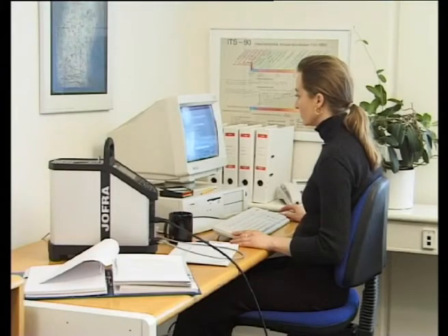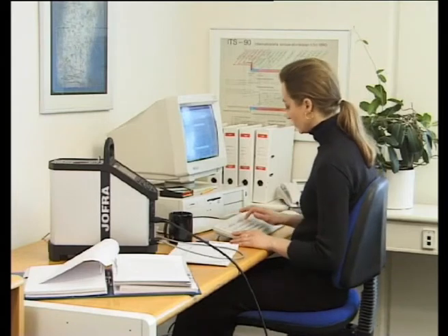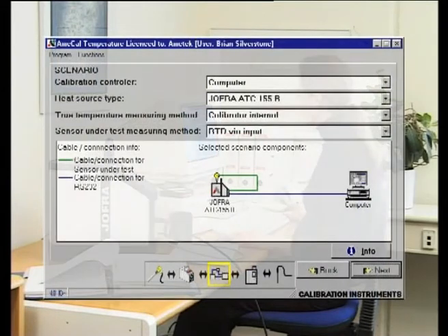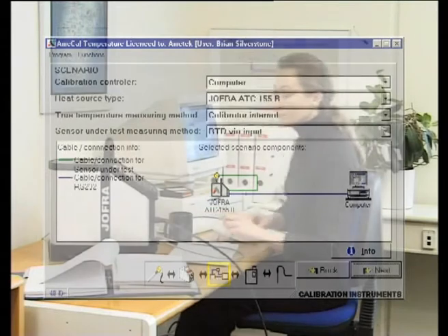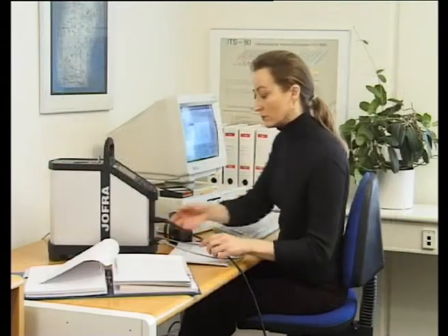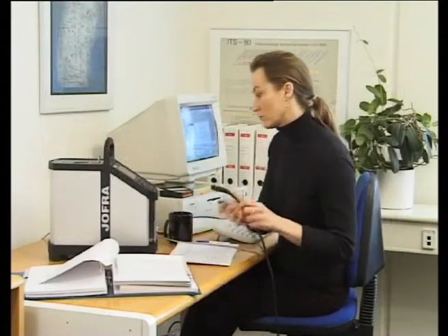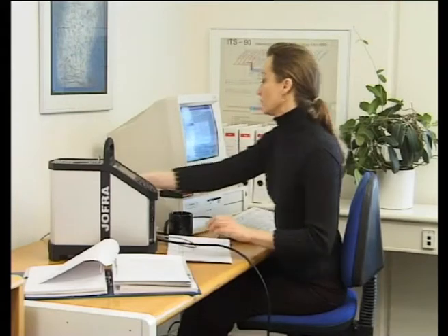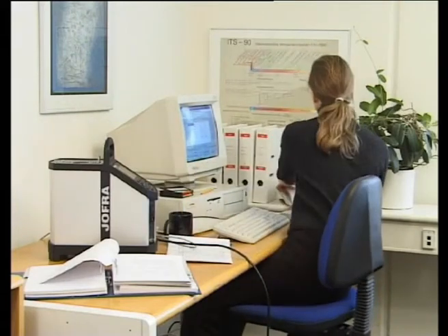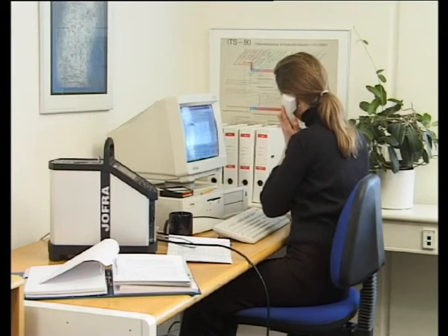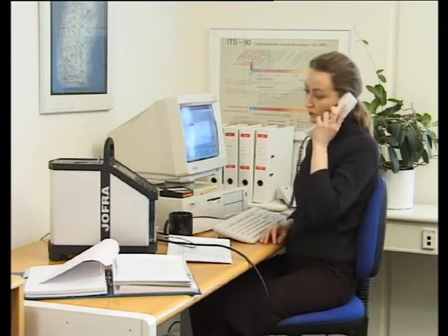You design all your calibrations in the Amcal temperature software. The relevant calibrations are collected together in work orders and downloaded to the calibrator via the RS-232 interface. The calibrator stores the calibration procedures and can be taken out to the process line without bringing the PC. This is beneficial to you from 2 standpoints.